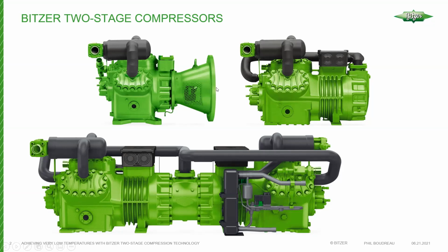So you can couple a motor to this. We have a semi-hermetic in the upper right, and on the bottom, what you're looking at is a tandem version of the two-stage compressor, and you can see that there is an economizer. You'll see the black box on the front of the compressor on the right-hand side there.